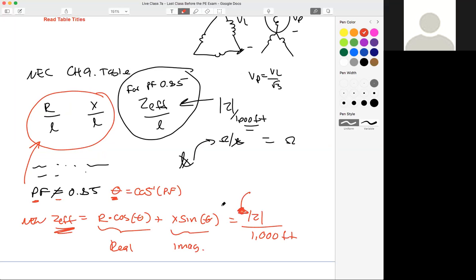Now here's the controversy. The controversy is a lot of the sample exams don't do this when they should. A lot of the sample exams, they'll take these R and X per L values, and they'll treat them like this: they'll just say, okay, my Z per length is R plus JX per 1,000 feet. And then they multiply this by their L to get their total impedance. They don't calculate a Z effective.